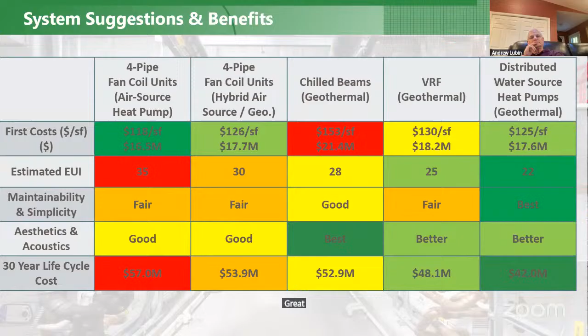Question regarding maintainability. When we talked last meeting about the distributed heat pumps, in addition to the square footage required for the individual closets, there was a conversation about needing to service an umpteen number of individual compressors throughout the building, whereas other systems had a centralized mechanical room with the heat pumps located in one place. Having run operations for a school district once upon a time, I would look at all of those individual compressors and the air handling equipment required for each to be on par with what we're looking for as far as a maintainability profile, as individual fan coils serving those zones as well.